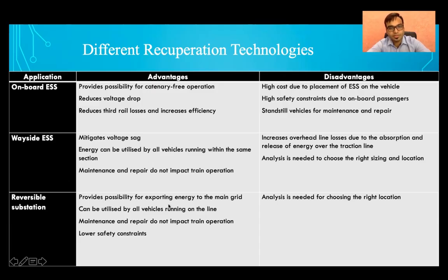The advantage of reversible substation is that it provides the possibility to export energy to the main grid. When energy is regenerated by the rolling stock, it is first fed to nearby trains, then through inverters it can go to the medium voltage network for use in auxiliaries. If the energy is further balanced, it can be fed back to the main grid for utilization by other utilities. This energy can be utilized by all vehicles running in the corridor, and repair or maintenance of the substation or inverter will not impact train operation, since there is no passenger safety constraint as it is not an onboard solution.